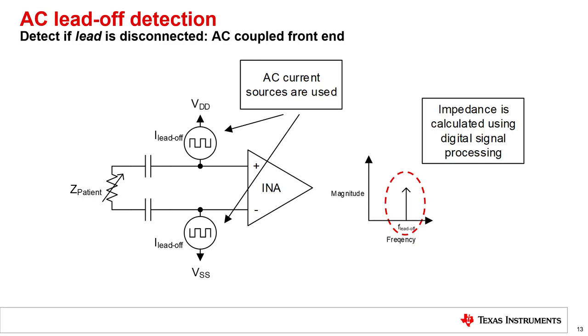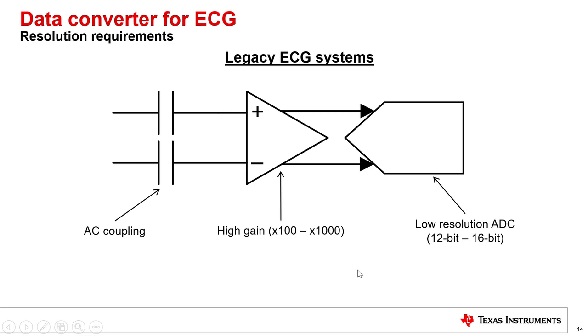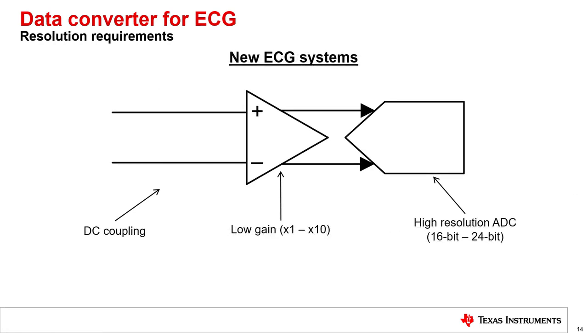The final stage in the ECG input signal chain is the analog to digital converter or ADC. Past ECG systems typically use cheaper low resolution ADCs. In order to get the input referred noise of the system low enough, the INA stage would need to be configured for a very large gain. This would not be able to tolerate the large offset voltage from the electrodes, so they would also need to AC couple the inputs in order to use large gains without clipping the ADC. New ECG systems take advantage of high resolution ADCs. They can afford to DC couple the inputs to the INA, use a low gain, and take advantage of the wide dynamic range of the ADC to measure a small ECG signal on top of the large DC offset.